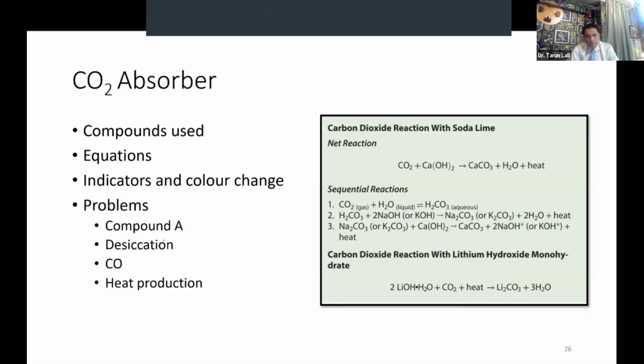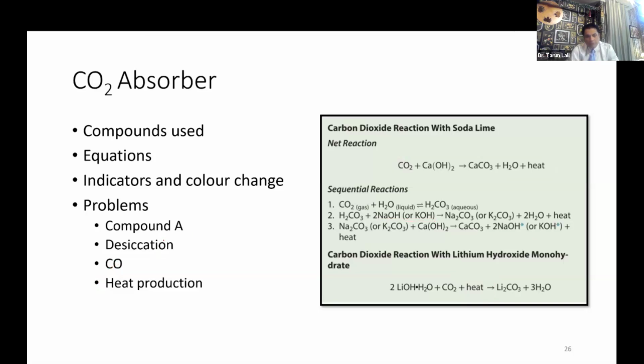So what is compound A? You all know it is produced because of reaction with sevoflurane, and it is produced more when sevoflurane is used for longer durations at low flows. The FDA recommendation is that flows with sevoflurane should not be less than 2 liters per minute. But recent studies have shown that even much lesser flows, 1 liter per minute, and some studies with even lesser flows, are safe in humans.